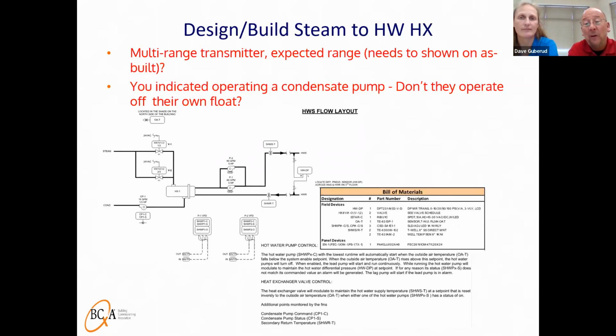Simple things like when they have multi-ranging transmitters, to make sure that people are adjusting them to the right pressure rating. This is oftentimes the case, like we'll say on differential pressure transmitters. Some of them have the adjustable range, and you do have to make sure that the range is high enough to be greater than or equal to what the pump head is in the first place. Otherwise, that value potentially can be clipped and only hit the transmitter ceiling. The differential on like a 0 to 25 transmitter might be less than the 25, but if the head is 50, you again knocked off potentially 25 PSI. So again, it's just simple little questions that we're wanting to ask.